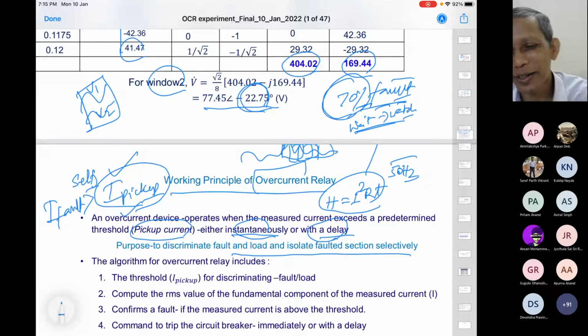Yeah. Let us say one day I was visiting the Kanpur campus, and in the morning walk I saw a bat on the live overhead conductor. At that time the campus had overhead conductors. So what would have happened? The bat, touching two phases, would get a 400 volt supply, and it will die. But that is a very small event for a strong distribution system. Whenever there is a short circuit, current will flow temporarily, but that doesn't mean the system should interrupt there. Even a monkey and so on. So it is momentary, and then it vanishes on its own. Many times a tree touches and then goes back again.